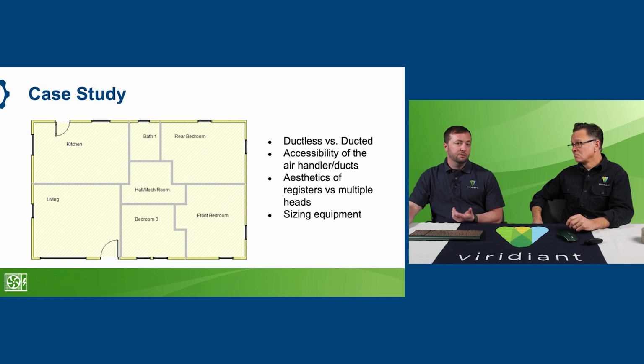The smallest capacity for most manufacturers is 9,000 BTU. For some, you can find 6,000 BTU. If you end up going with that standard 9,000, then you've installed 45,000 BTU of capacity, which, having done a Manual J calculation, is over twice what's needed. While the equipment is variable capacity, it's a whole lot of extra capacity that the homeowner has to pay for. It also introduces a problem of likely not having enough moisture removal ability.